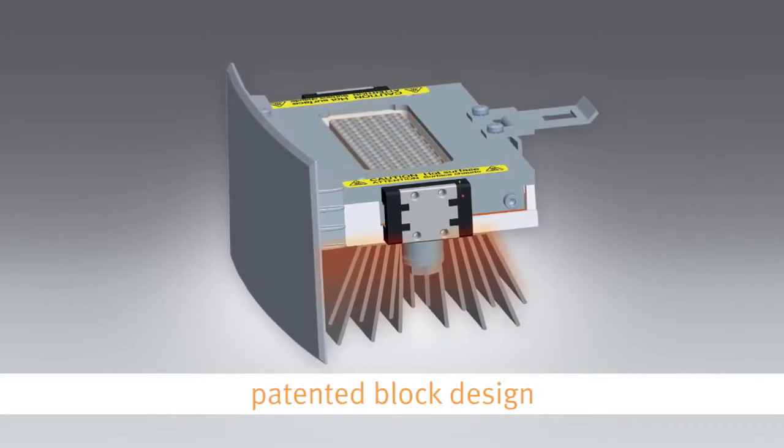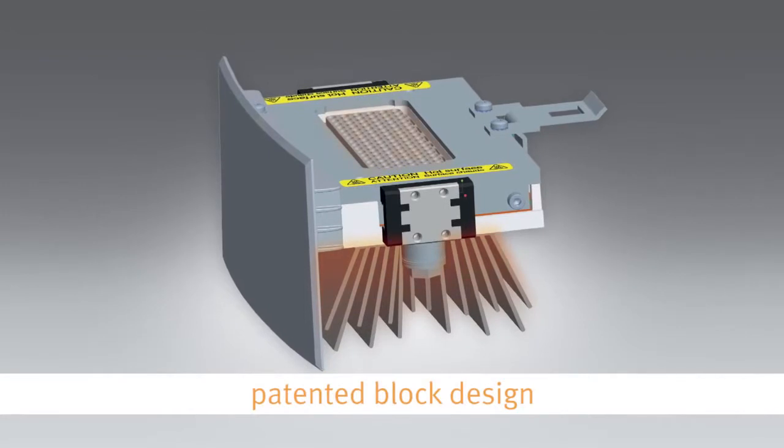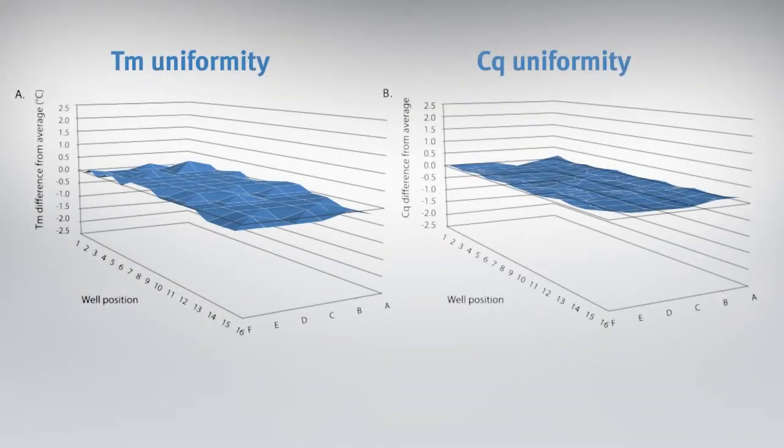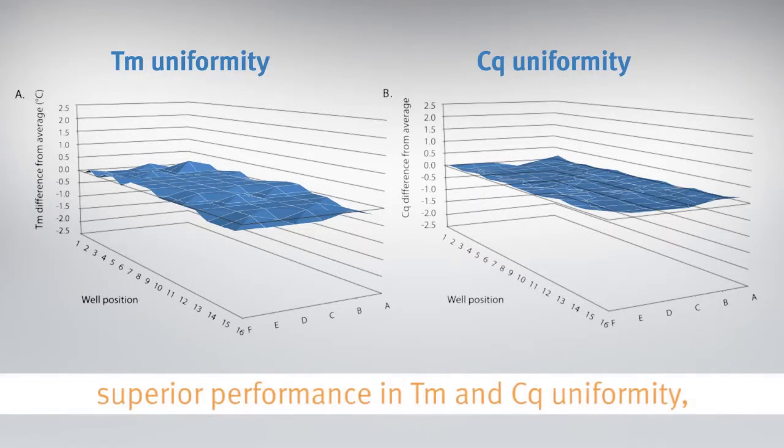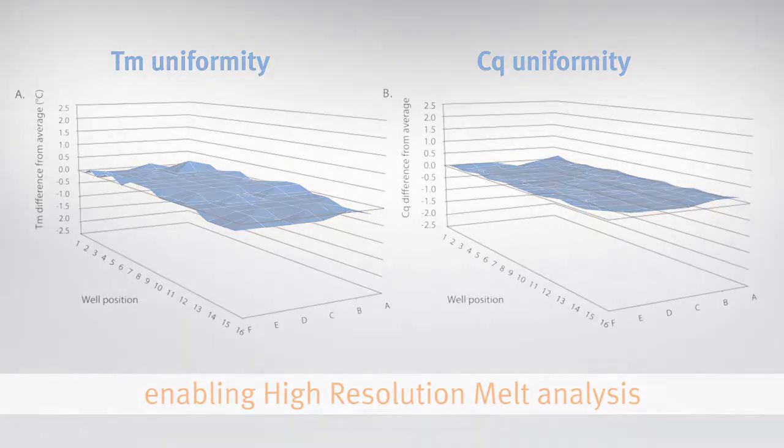The unique patented block design of the PicoReal system ensures quick heating and heat removal over the entire plate area. With ultra-thin wall plastics, the target temperatures are achieved rapidly and the temperature homogeneity performance is outstanding at all three stages of thermal cycling. The uniformity of Tm and Cq are outstanding over the entire plate area. Therefore the quality of your data is ensured, independent of application and protocol.